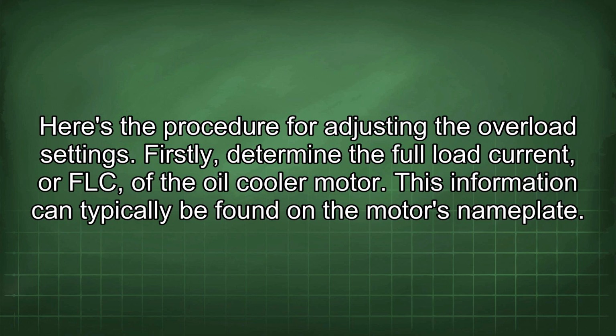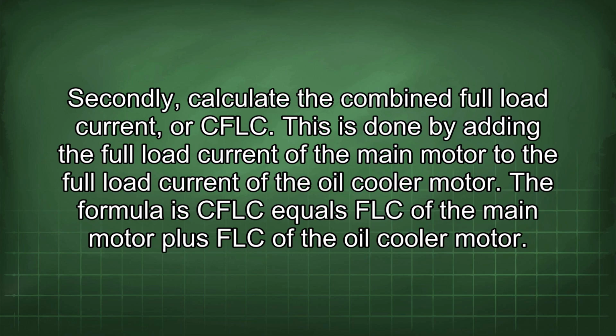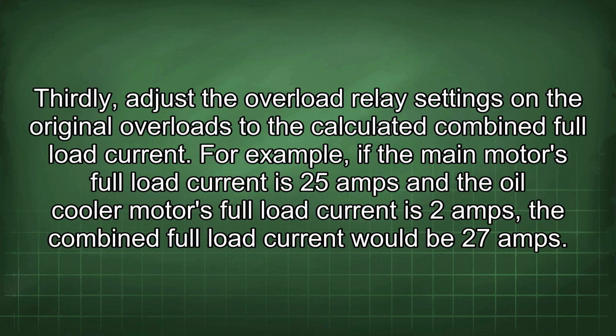Firstly, determine the full load current, or FLC, of the oil cooler motor. This information can typically be found on the motor's nameplate. Secondly, calculate the combined full load current, or CFLC. This is done by adding the full load current of the main motor to the full load current of the oil cooler motor. The formula is CFLC equals FLC of the main motor plus FLC of the oil cooler motor. Thirdly, adjust the overload relay settings on the original overloads to the calculated combined full load current.